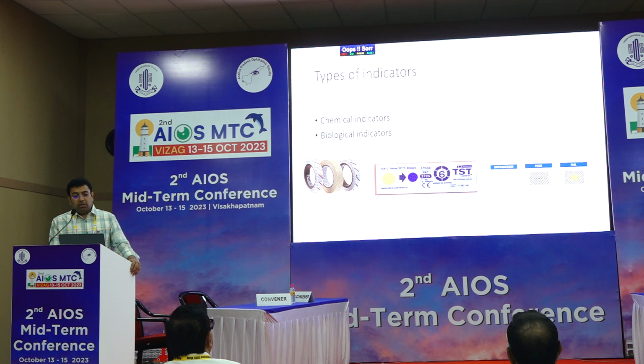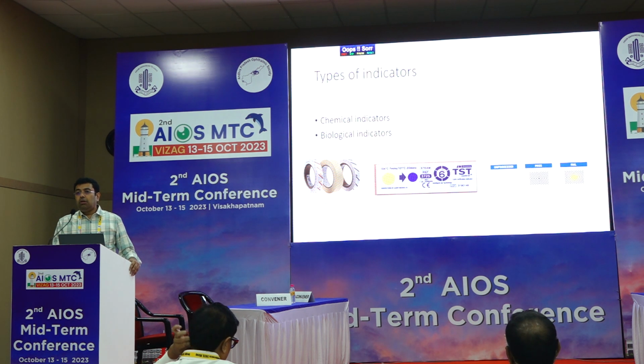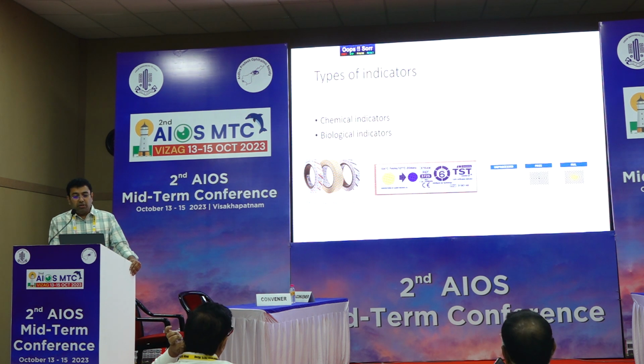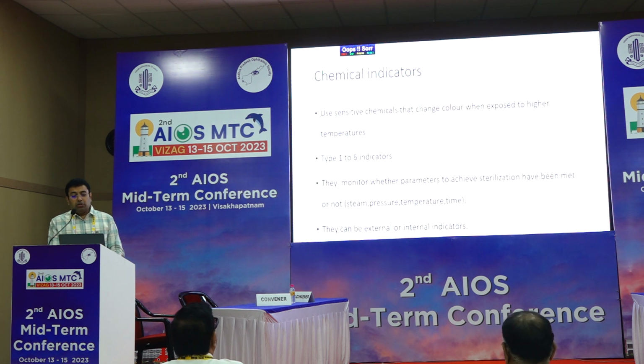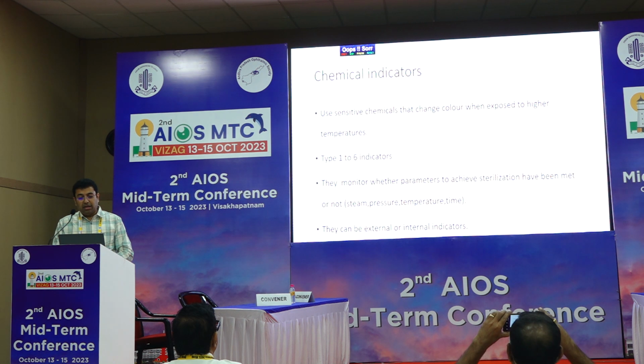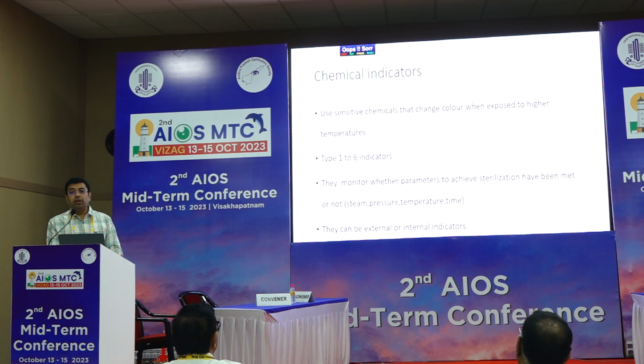So now coming to the types of indicators, you have to validate your sterilization process. There are two types of validating procedures. One is a chemical indicator and the other is a biological indicator. Chemical indicators use sensitive chemicals, and they change color when exposed to higher temperatures. There are 6 types of chemical indicators, type 1 to type 6, and they monitor the parameters of sterilization like steam, pressure, temperature, and time.